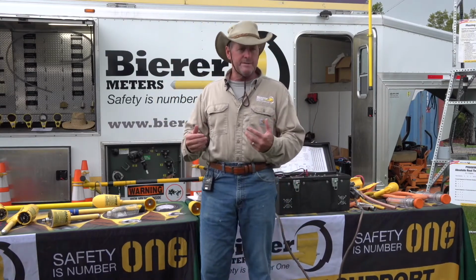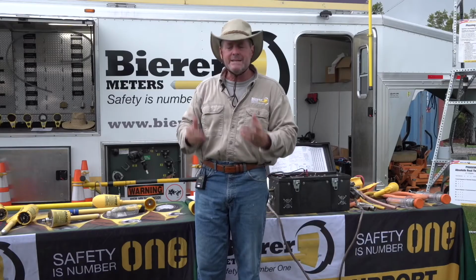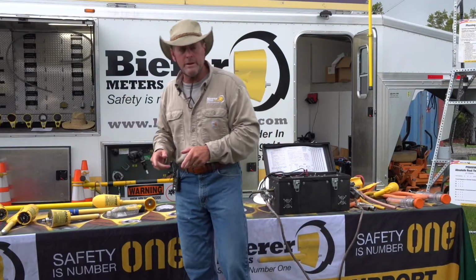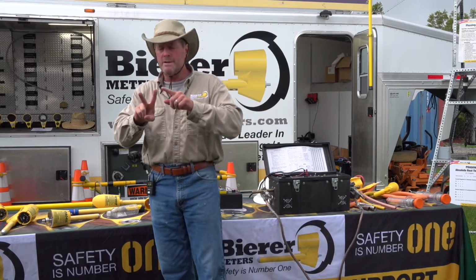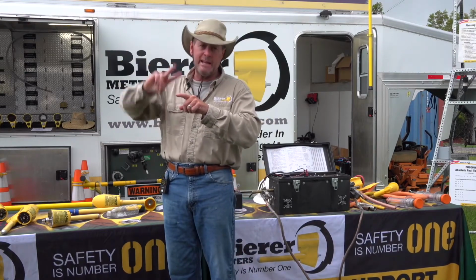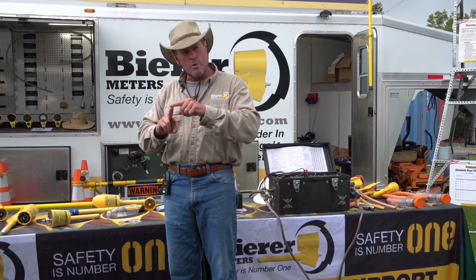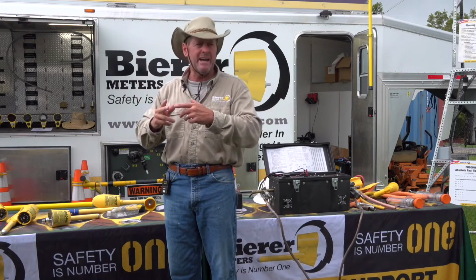He said, hey, we've got some long grounds that we use on our higher KV transmission lines, but we use the same set on our lower KV transmission lines, so we've got extra length. What I've been doing is coiling those up and taping them and letting them hang. And it's like, dude, we just had the training. You've got to tell your employer to buy you 2 sets of grounds: the long set for the higher KV transmission line, and a shorter set for your 69, so you don't need to coil up the extra cable. Get 2 sets, it's okay, it's a lot safer.